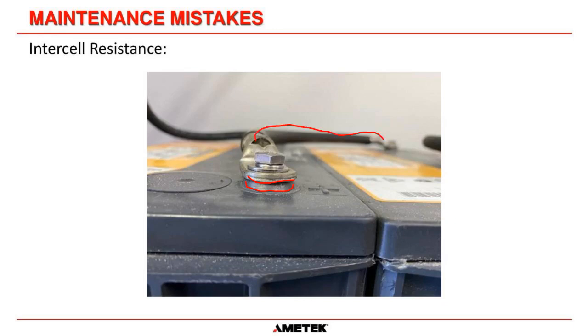We cannot have it touching the lug here, because then all you'll be measuring is the resistance of the cable. We need to measure from the lead and this connection resistance between the lead and the lug, and then over here between the lug and the lead.